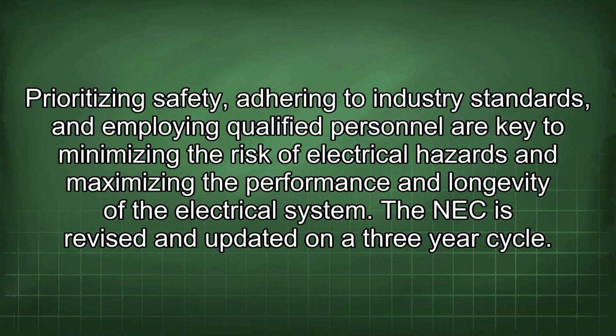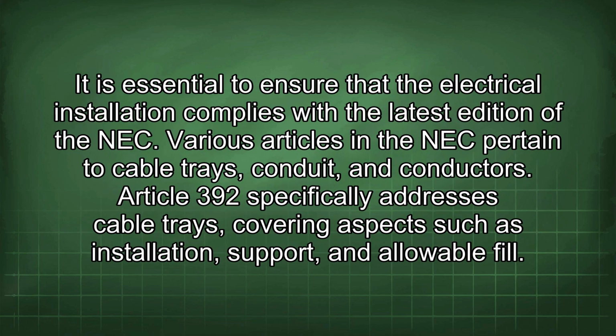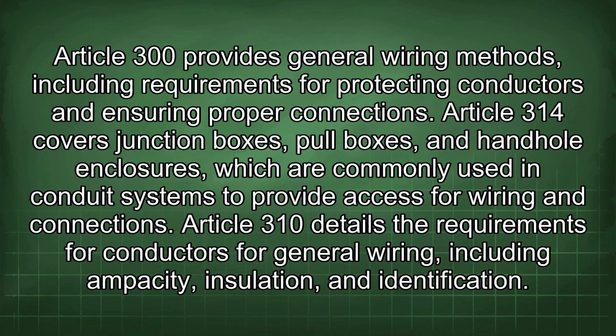The NEC is revised and updated on a 3-year cycle. It is essential to ensure that the electrical installation complies with the latest edition of the NEC. Various articles in the NEC pertain to cable trays, conduit, and conductors. Article 392 specifically addresses cable trays, covering aspects such as installation, support, and allowable fill. Article 300 provides general wiring methods, including requirements for protecting conductors and ensuring proper connections.